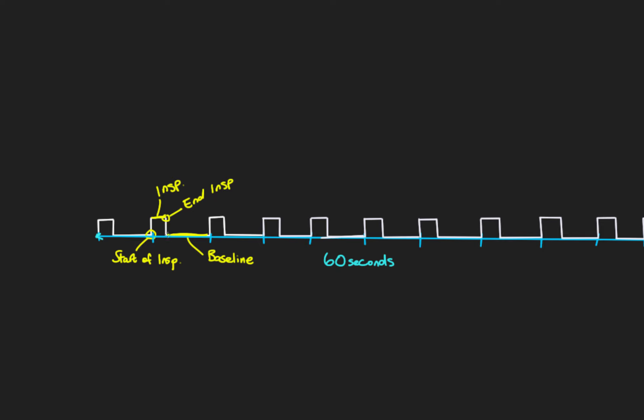I just want to add one thing to the baseline comment: it is acceptable to call this a baseline phase, but it may be easier to also view this as the expiratory phase. When looking at pressure, it makes sense to call it a baseline because it is a baseline pressure in the circuit. But this really is the expiratory phase. So let's label those — in pink for expiration, and green for inspiration.